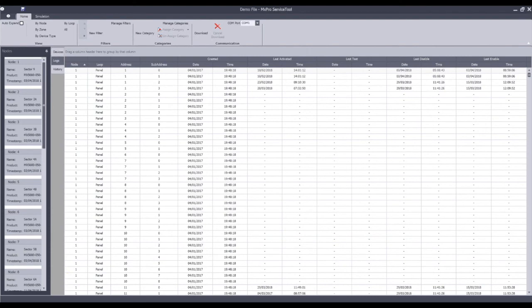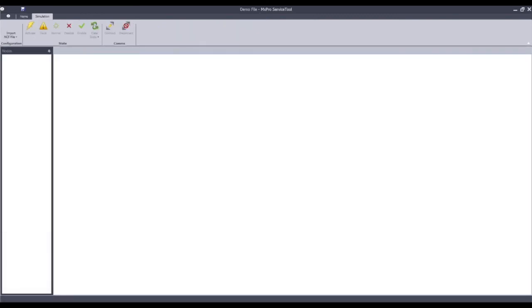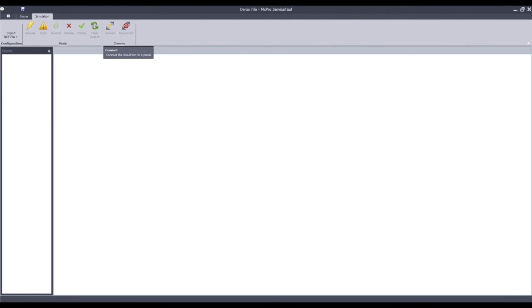That finishes the summary of the device, the logs, and the history. The second function of the service tool is a site simulation feature. This allows you to connect to a Pro 5 panel on site or in your office — which is at level three in commissioning — open up a configuration file from the actual site or one that you want to test and validate, and it will then allow you to connect to the control panel and use the service tool PC itself as a virtual network. Your PC pretends that it is the system and you can actually activate a device on the PC and see how the panel you are connected to will react — for example, when you activate a specific call point, does the door relay open? If you have a fault from a certain device, does something happen on the system?